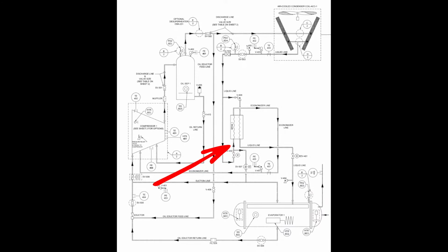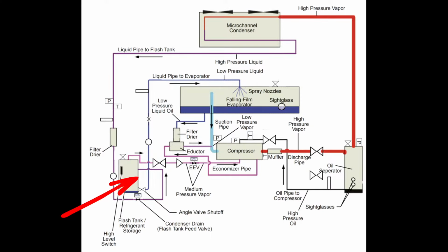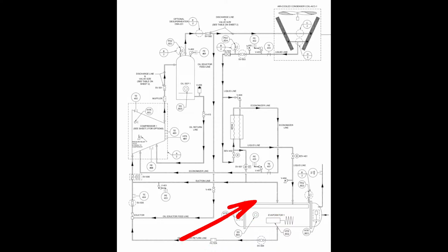And that is different than what we saw with the style A machines, where both circuits shared the same evaporator. The evaporator on these was split down the middle, if memory serves. So the evaporator was split in half internally, but they all shared the same evaporator shell and whatnot. That's on the style A, whereas on the style B, we actually have independent evaporators. So if you want to know which style you have, those are the two big things you're looking for. One, do I have one solid evaporator or two independents that are run in series? And two, do I have a flash tank or a braze plate? Those are the key things, and that's going to change significantly what potential problems you could have, how you're going to need to troubleshoot this, and how you expect this machine to function. This has a major impact.